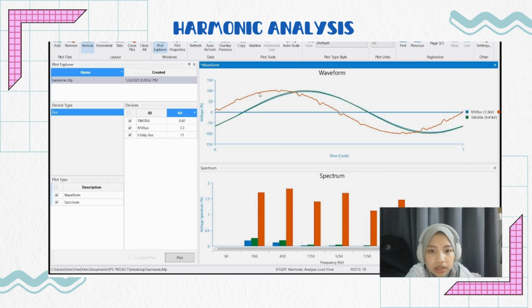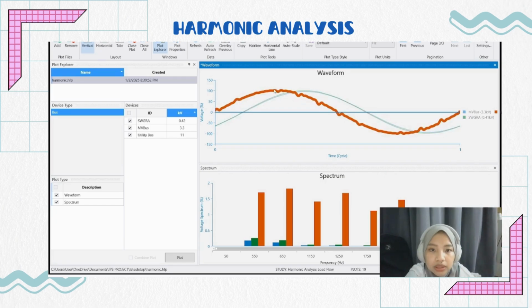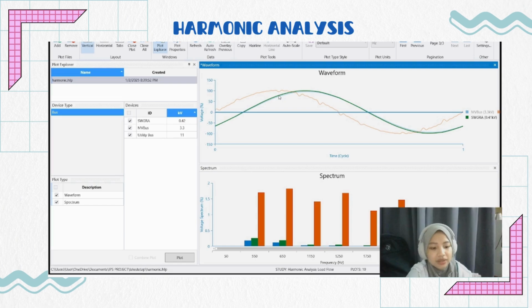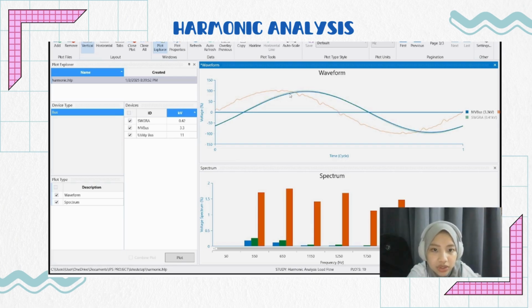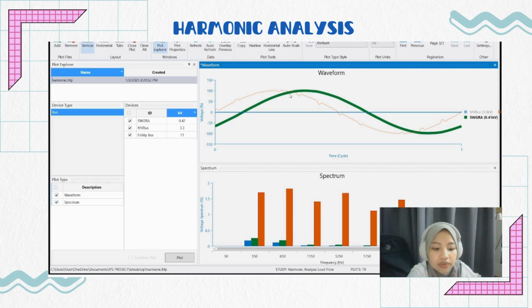The highest amplitude is led by the orange line, but it is not perfect because it has a lot of noise. For the green line, which is the SWGRA bus bar, it follows with slightly lower amplitude but has a stable and perfect sinusoidal shape with less distortion. The blue line, which is the MV bus bar, has the lowest amplitude compared to the others with minimal distortion.